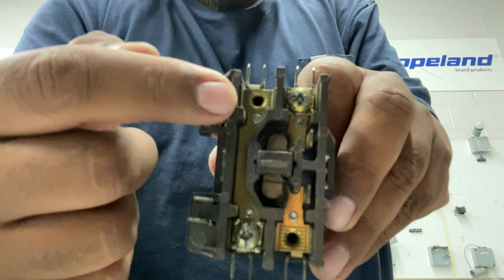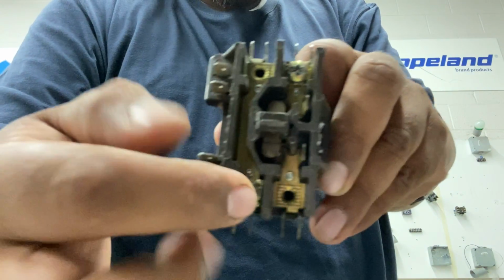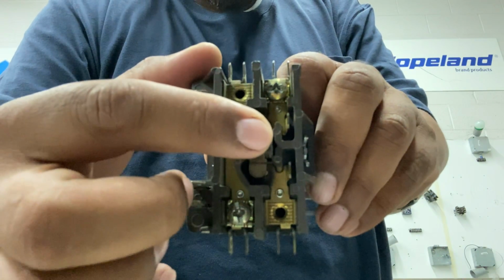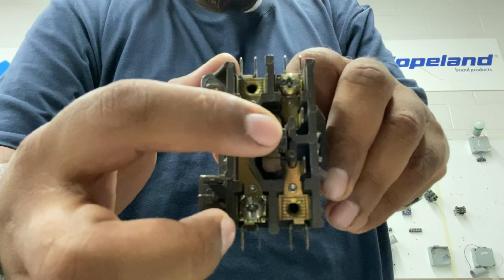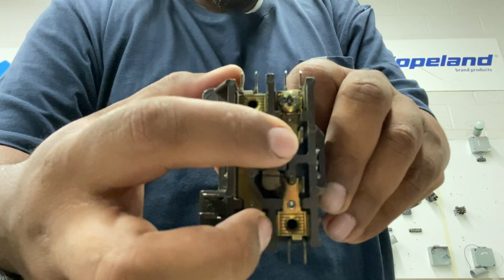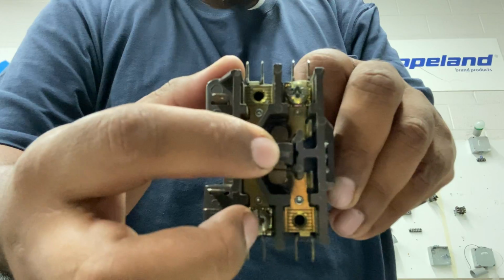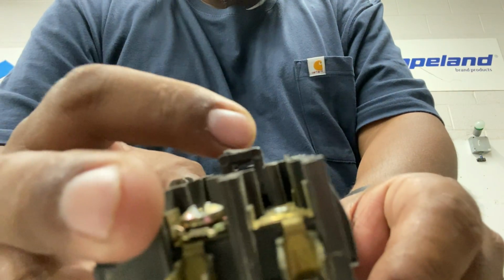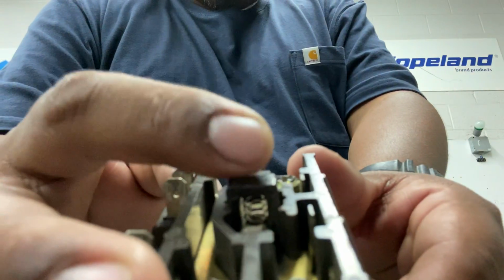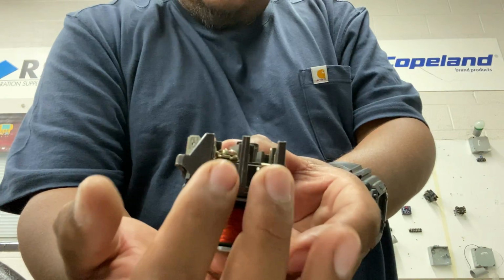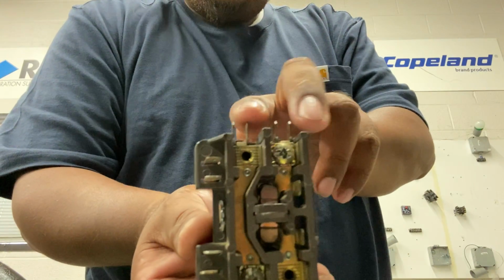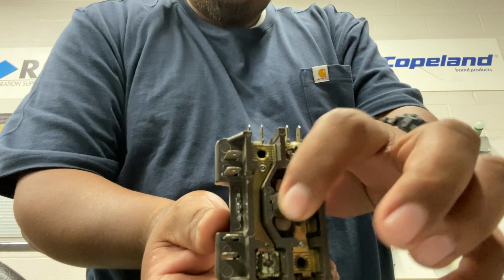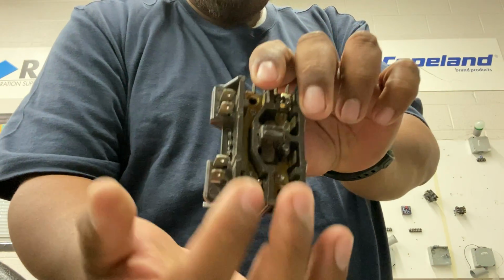So if we look on this side, it's a straight piece of brass that comes straight across. And on this side it hits a set of contacts, and then another set of contacts here. Well, this guy here, you guys can see it's right here. It's pointing over here, but it's here, all right? Once you push this guy down, see if I can get a better angle on this. Once you push this guy down, it closes that set of contacts. So after this guy gets pushed down, it basically acts like this solid piece that's on this side, all right? It basically allows power, incoming power that gets hooked up here, right, to get sent up here. So after this set of contacts closes, power is up here.